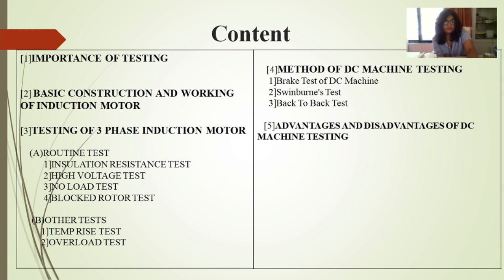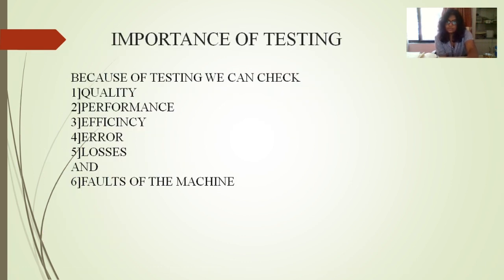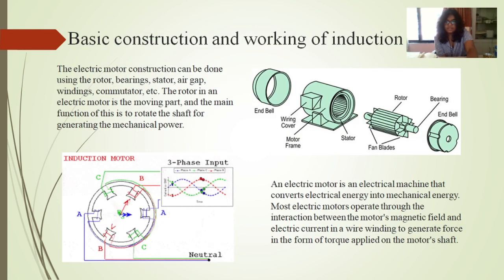The first will be the brake test of DC machine. The second will be the Swinburne's test. The third will be the back-to-back test. And at the end, we'll be learning about the advantages and disadvantages of the DC machine testing. So the importance of testing is so we can check the quality, the performance, the efficiency, the errors, losses, and different faults in the machine. This also overall makes the maintenance cost less if we test it regularly.